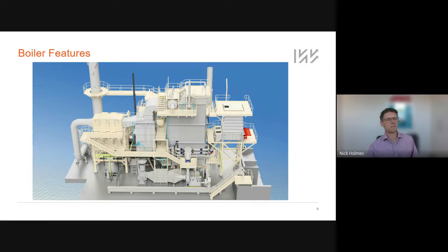Obviously, combustion air is a big component. So you have a forced draft fan, which goes through a big preheater to elevate the temperatures before the air gets into the furnace. This design has a lot of layers of overfire air to get all that turbulence into the furnace, just like blowing your fire when it's time to go out. It ignites, gets the oxygen into the fire and stirs it up. So that's the idea with the overfire air.